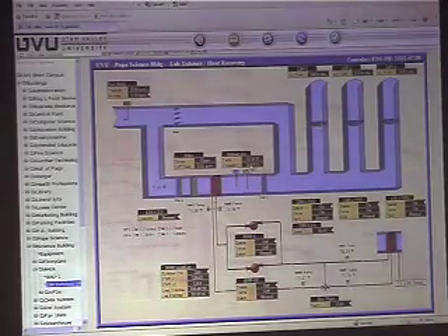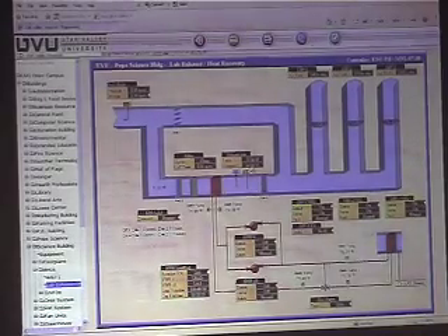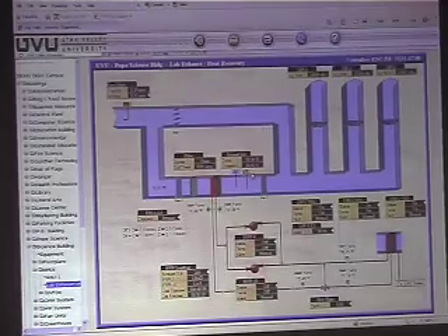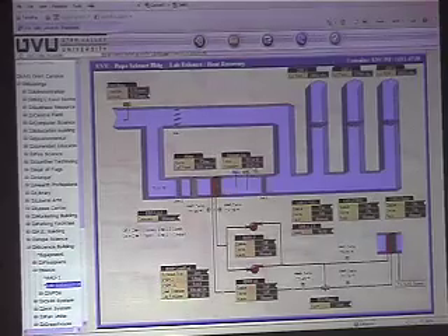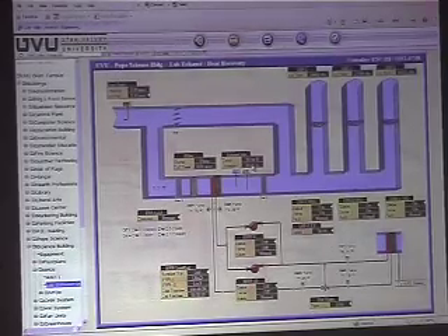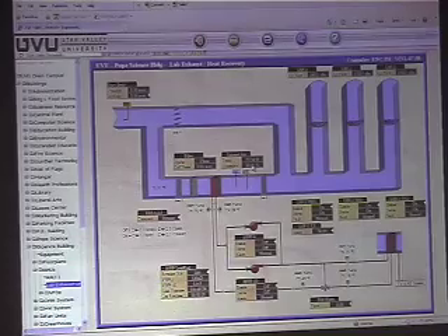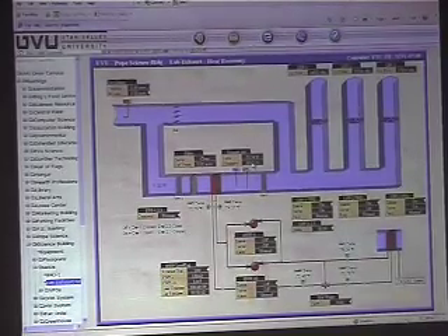Exhaust air humidity right here. Even though it says exhaust, it is the return air humidity from the building that we're picking up. So if this gets above 50%, it'll lock out the direct evap section and we just sequence to the chilled water.